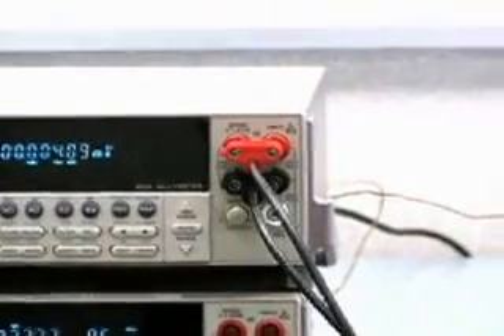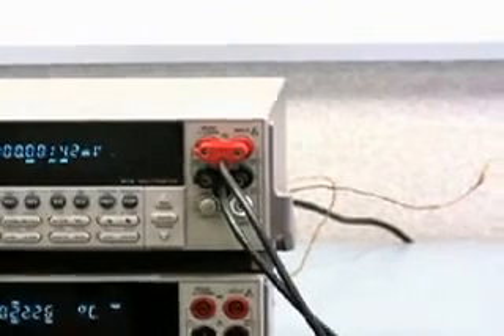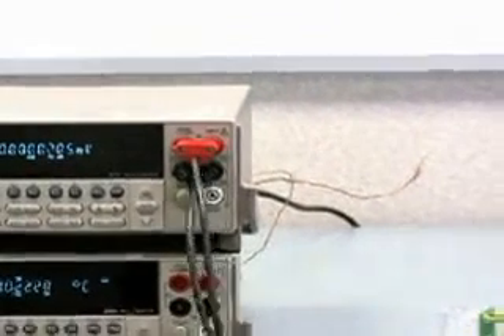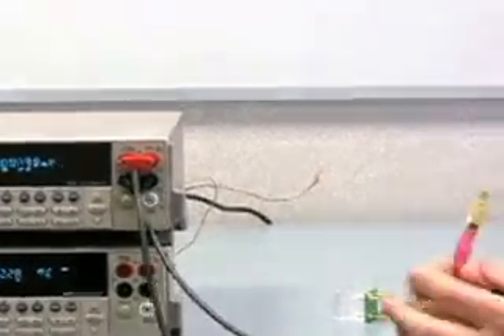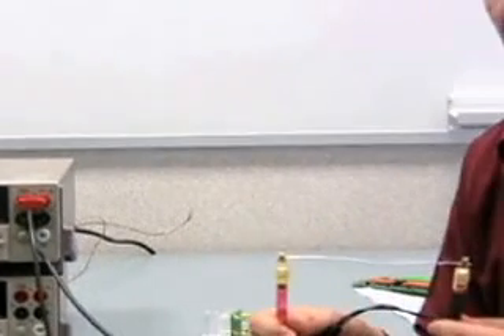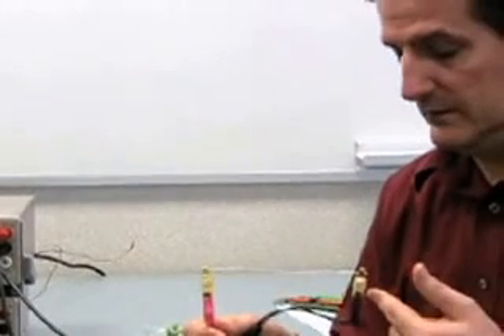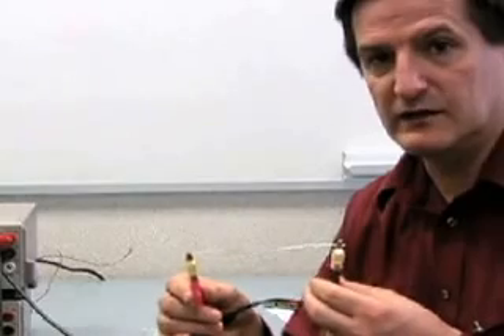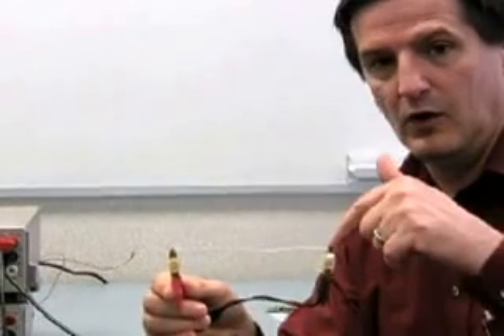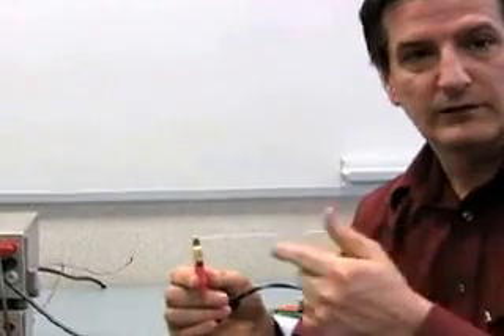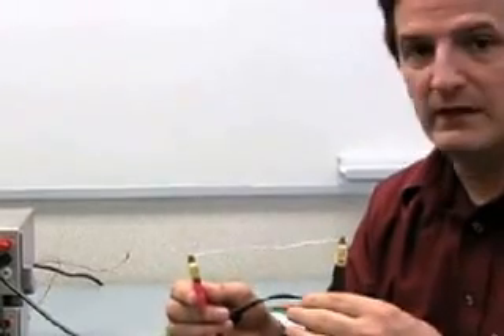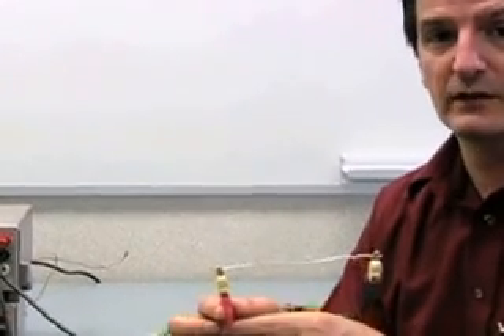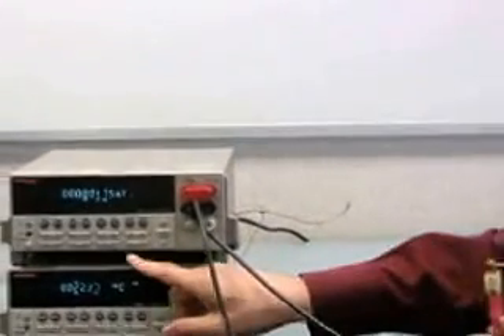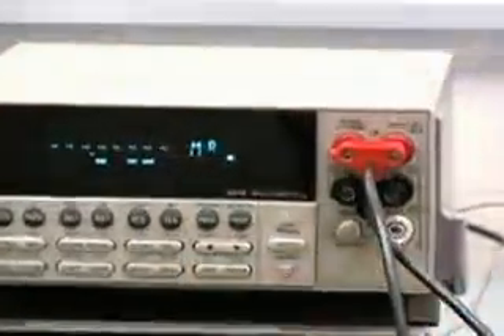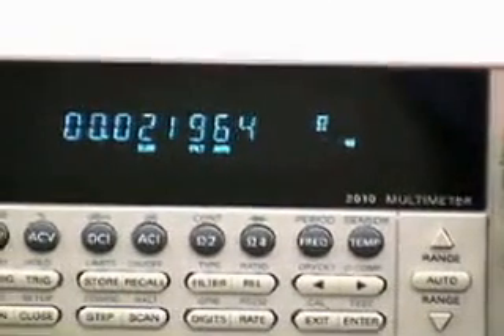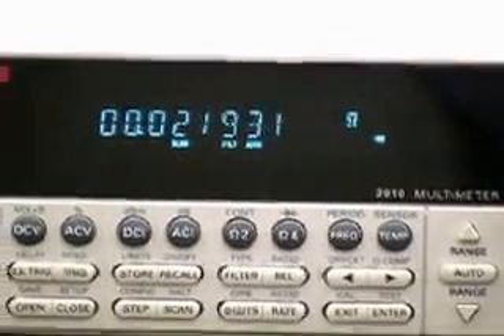And I will select four wire ohms, but in a minute, I want to show you what I'm going to measure. This is a standard paper clip. I unraveled it, and I have the four wires on each end, the low and the high. A standard paper clip is normally about 20 milliohms. Let's take a look and see. Let's look at the front panel. I will select four wire ohms.